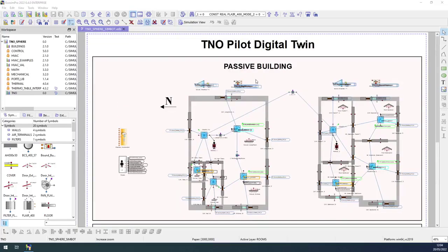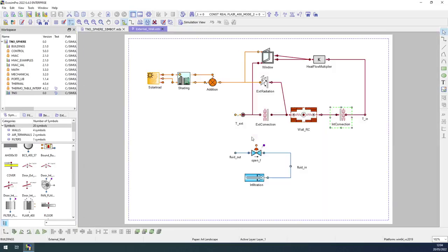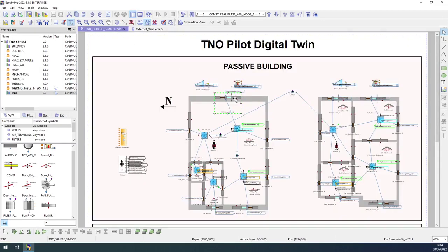The passive building model replicates all the heat transfer phenomena occurring in the building, whether through conductive, convective, or radiative processes. In addition, it takes into account the effects of solar radiation and the shadows generated by adjacent buildings. Moreover, the effect of air infiltrations through windows and doors can be calculated. The passive building model is composed of external and internal walls, ground, roof, and room volumes.